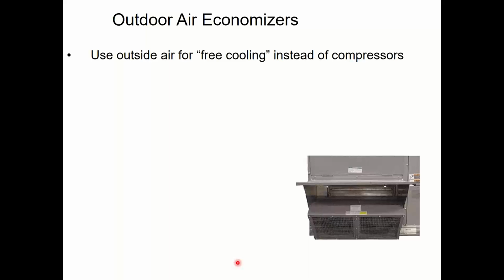All right, outside air economizers. This is really important because this is probably the third best thing that I could do to save energy in a building. Putting it on a schedule is probably number 1 because it's super inexpensive to do that. Getting the fan to be more efficient, which we'll talk about next week, is probably number 2. And then getting this free cooling is probably number 3. So a lot of commercial buildings need cooling when it's cold outside.